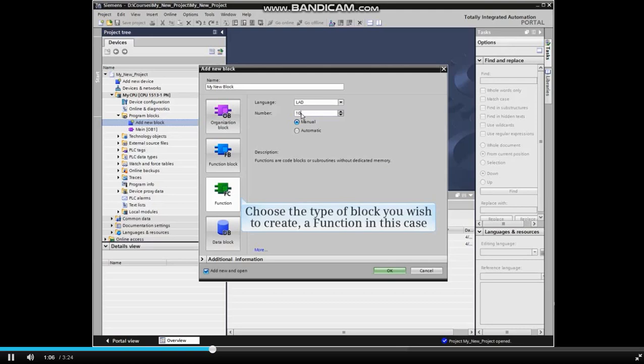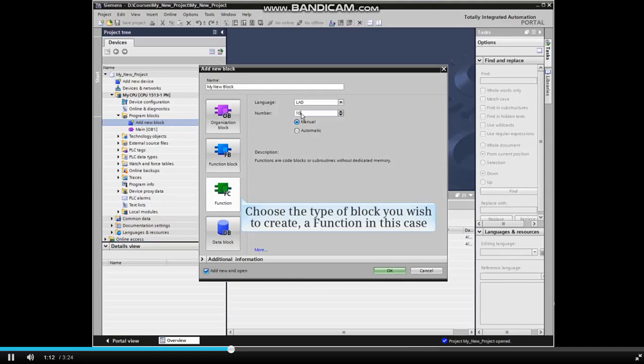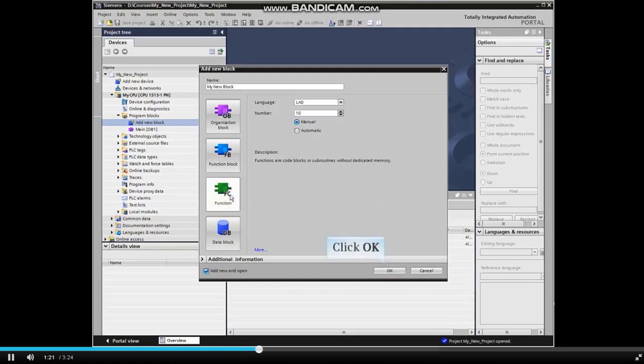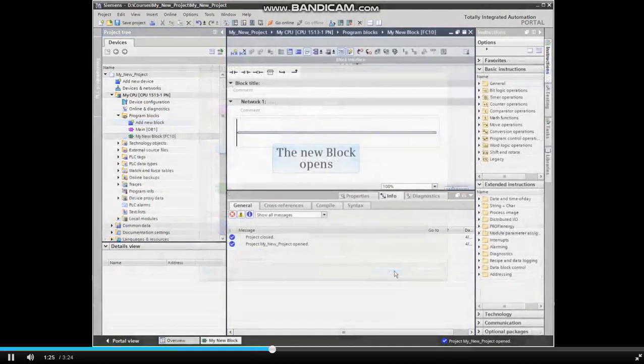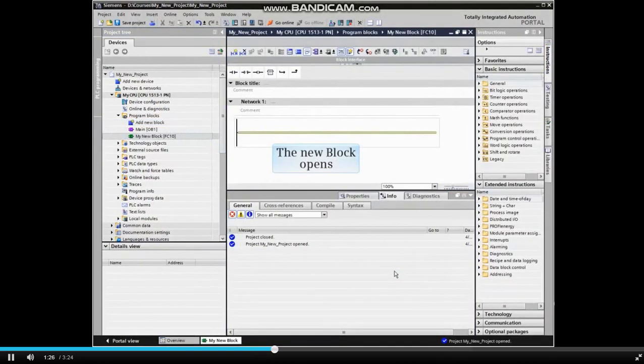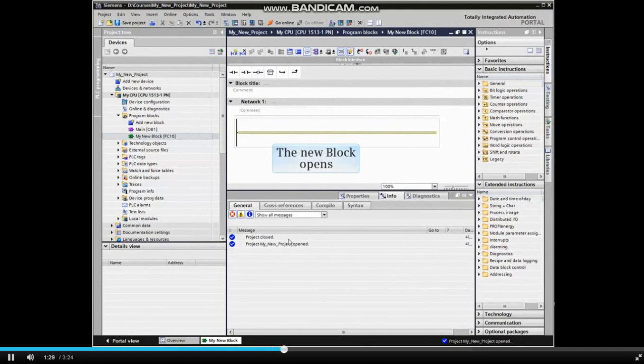You must choose the type of block you wish to create: an organization block, function block, function, or data block. We'll create a function in this example. Click the button for a function, then click OK to create the block. The new block opens with ladder programming language as we selected.